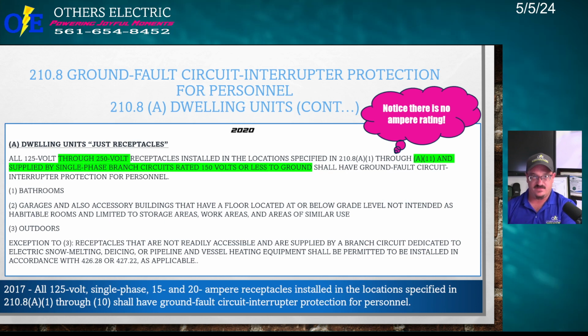So now in Florida, we got it. This is very important. So in dwelling units, now this is just receptacles, because I want you to know that. So 210.8A is just receptacles because it says right here, all 125 volt through 250 volt receptacles installed in the locations specified in 210.8A1 through A11 and supplied by single phase branch circuits rated 150 volts or less to ground shall have ground fault circuit interrupter protection for personnel. That's the major change. One is they added A1 through A11. The second is they changed the voltage through 250 volt.